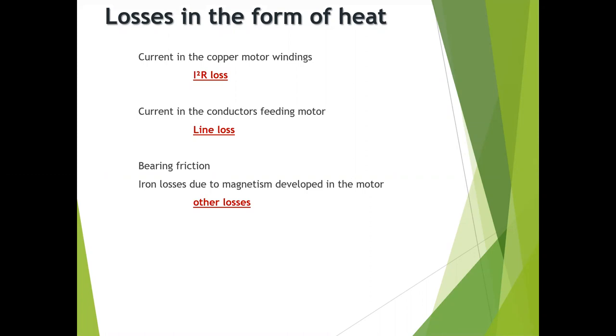You see how we have three different types of losses in the form of heat depending on what part of the circuit we're talking about. When we get to the specifics, I squared R losses refer to the copper motor windings, line loss is the conductors feeding the circuit, and bearing friction and other types of losses that develop due to heat would just be other losses.